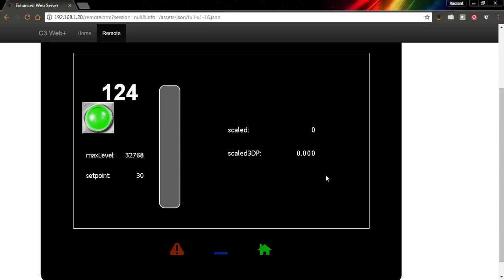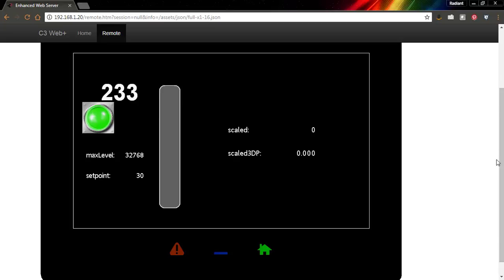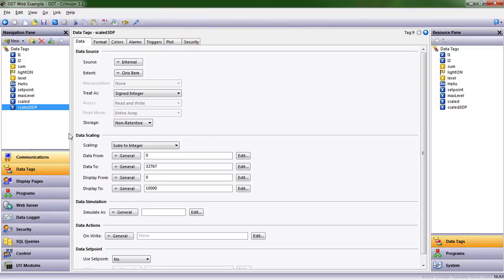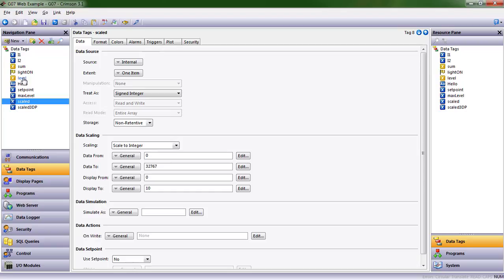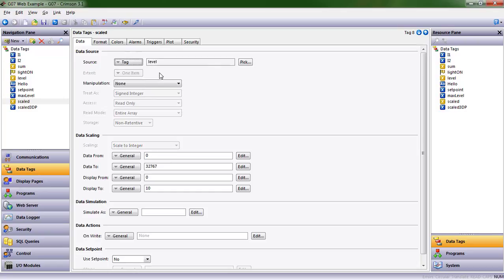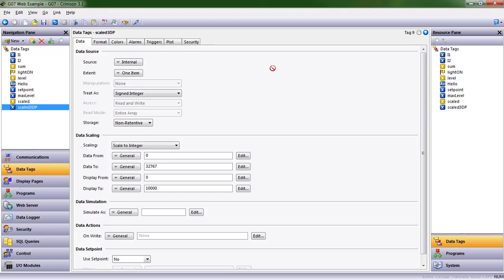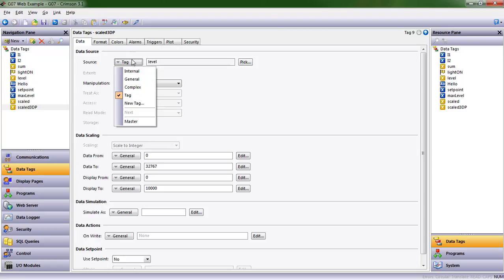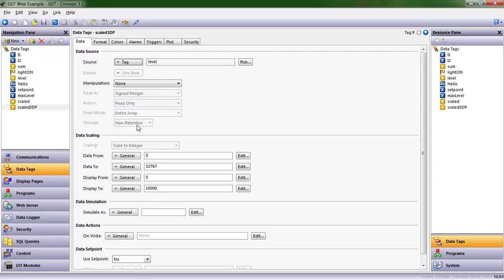We just set up the data tag, but we never told it what analog input we were looking at. Let's come back over. Scaled and scaled 3DP are actually looking at this level tag. We have two ways we can do it. We can type in the word level, or we can drag level over from our resource pane. In a real application, you might be pointing to a register value, an input from graphite modules, or E3IO. For our purposes, we're pointing at that level data tag.